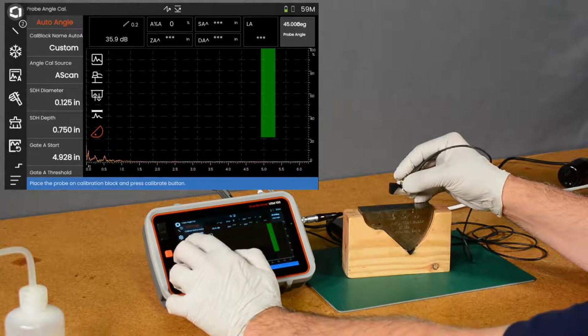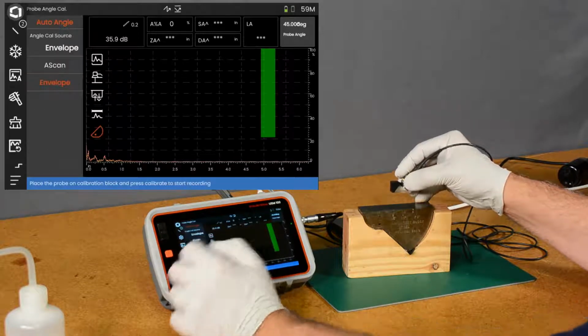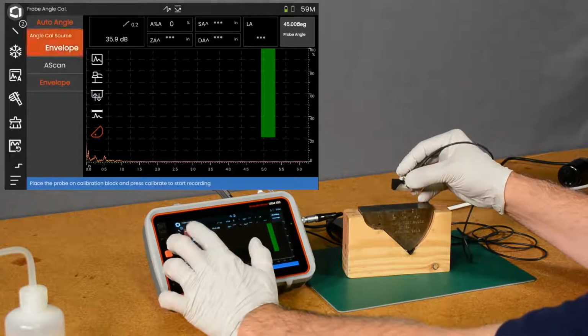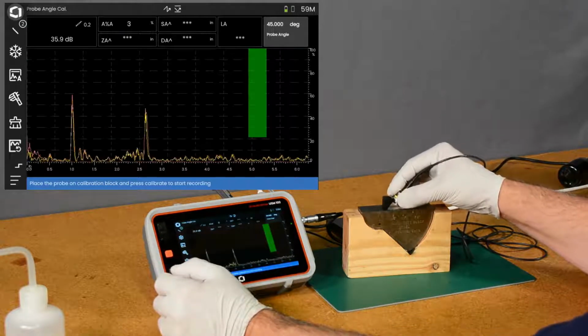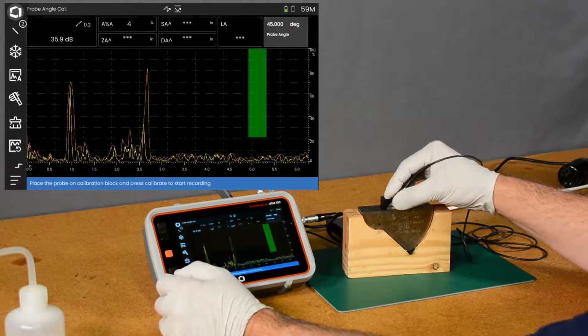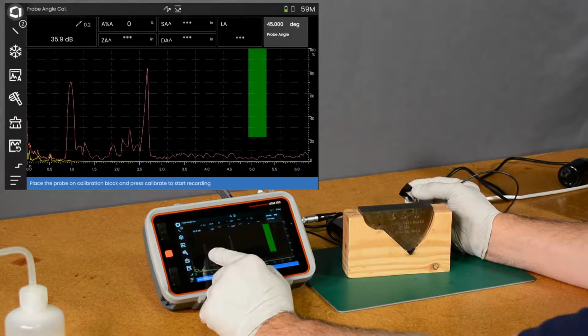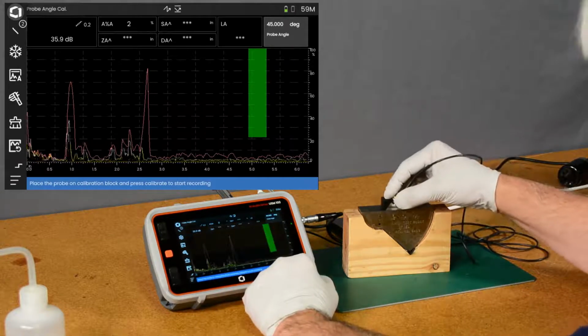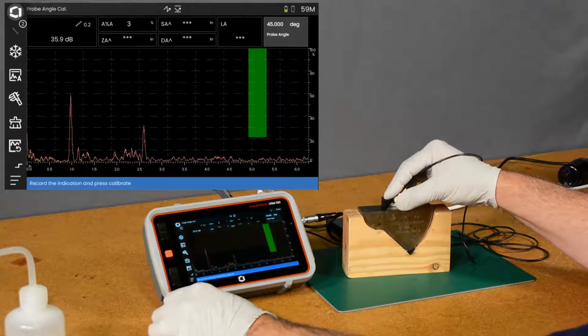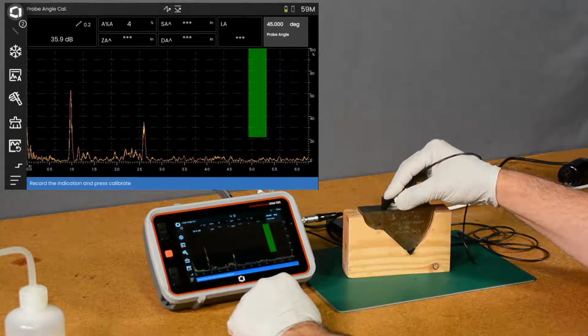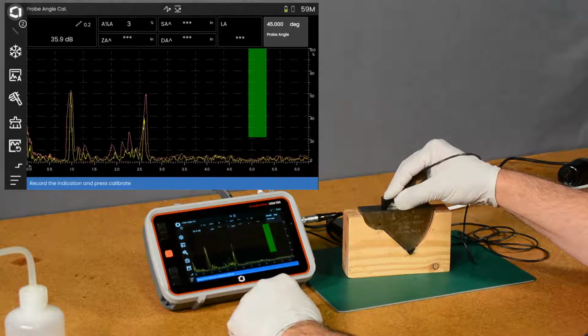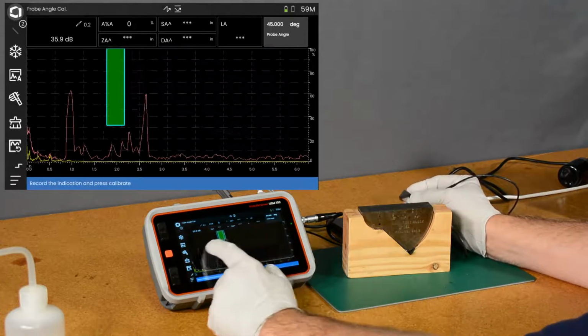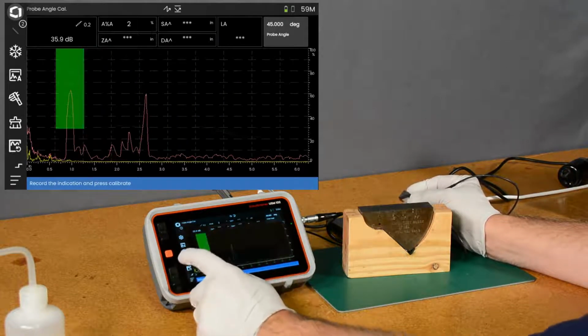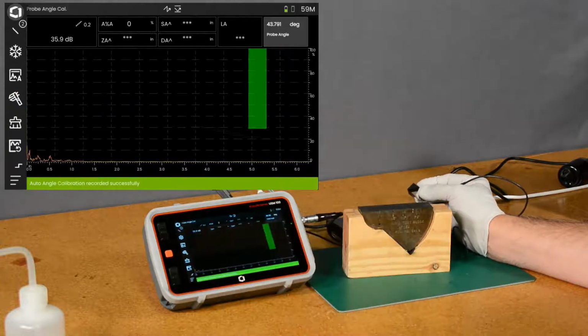Now, I can change my angle calibration source from A-scan to envelope. And by doing that, I've told it that rather than gating on the live echo, what I want it to gate on is this envelope peak that I've found. So now I can come in here, let's start our calibration, and it says record the indication and press calibrate. So what it's doing is giving me an opportunity to record where my peak is. Okay, I do that, bring my gate over that peak, I hit cal, and 43 degrees.